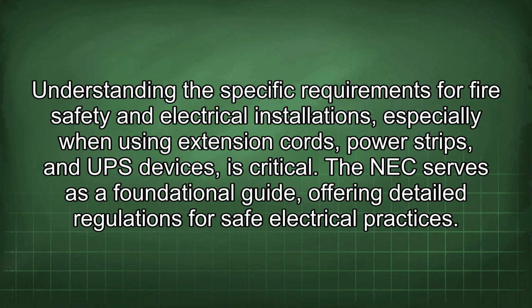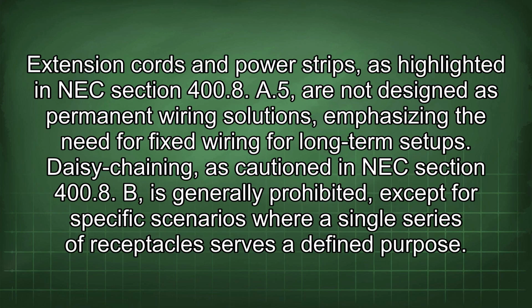Understanding the specific requirements for fire safety and electrical installations, especially when using extension cords, power strips, and UPS devices, is critical. The NEC serves as a foundational guide, offering detailed regulations for safe electrical practices. Extension cords and power strips, as highlighted in NEC section 400.8(a)(5), are not designed as permanent wiring solutions, emphasizing the need for fixed wiring for long-term setups.